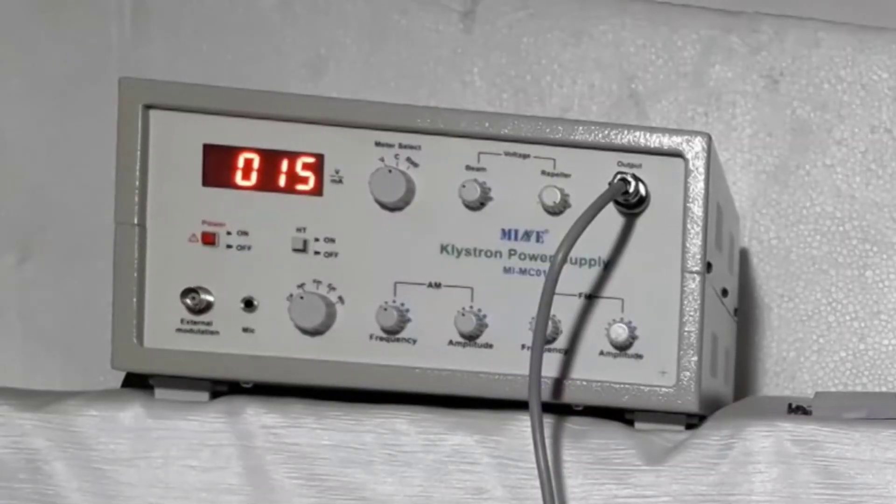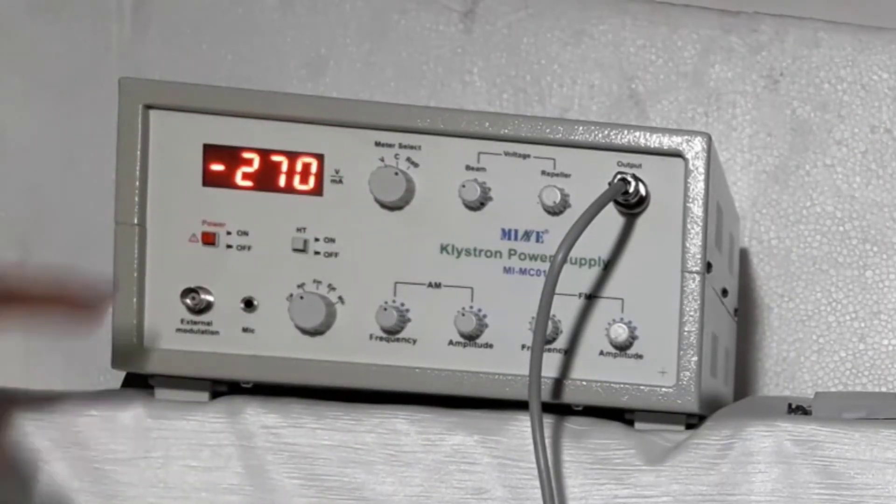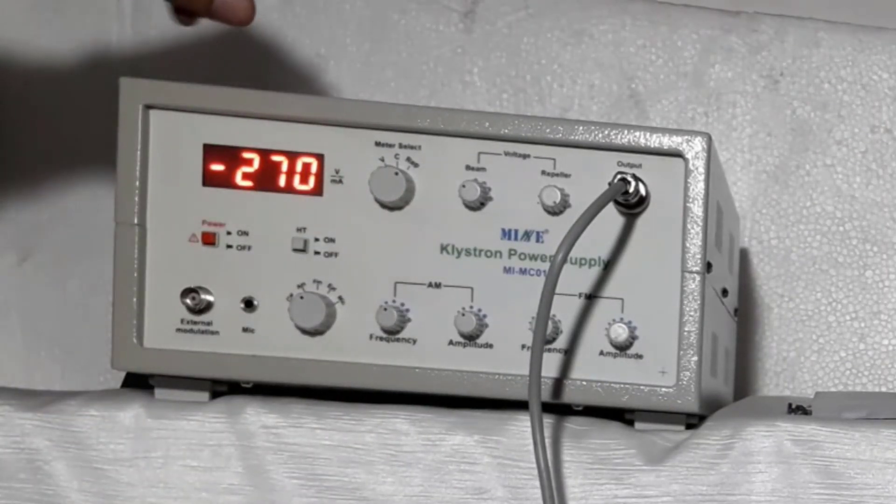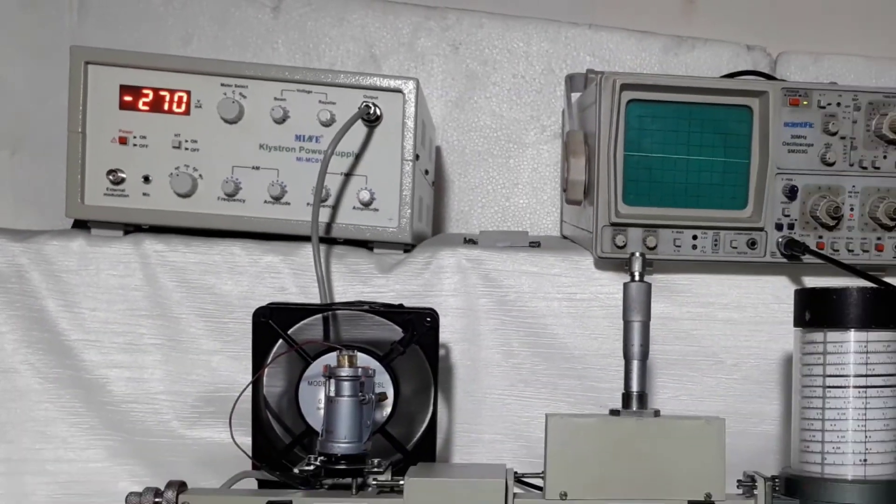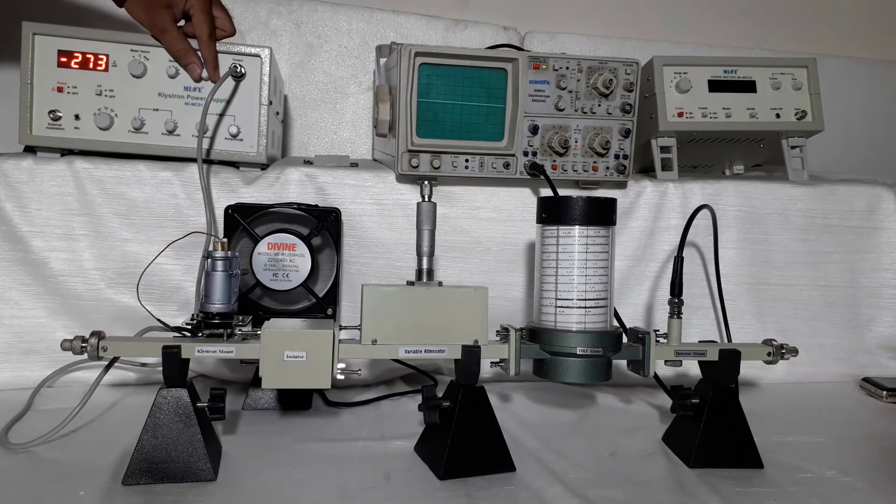Now change meter select knob at repeller voltage and see repeller volt. It would approximately minus 270 volts. Now by changing repeller voltage clockwise slowly and try to get a square waveform on CRO.